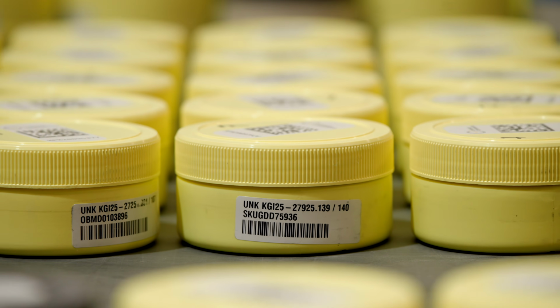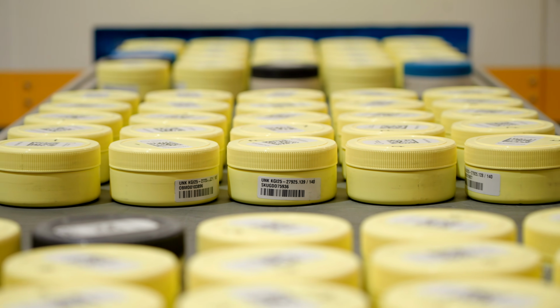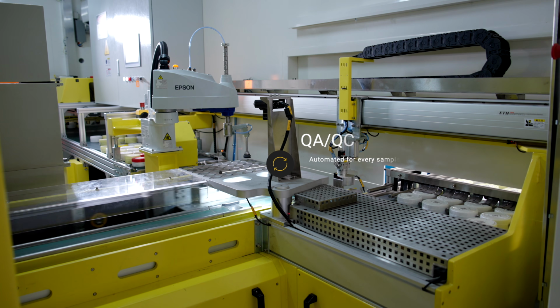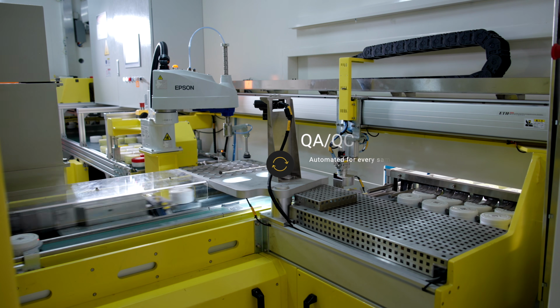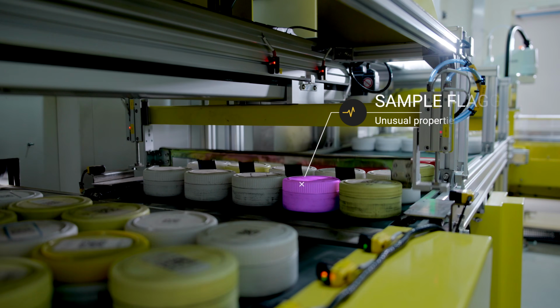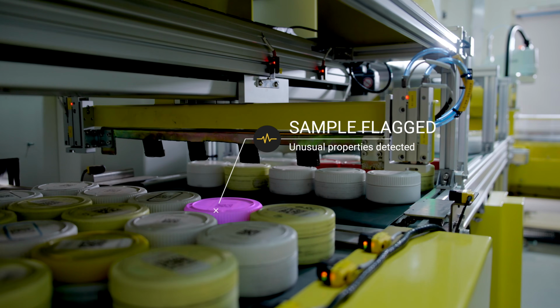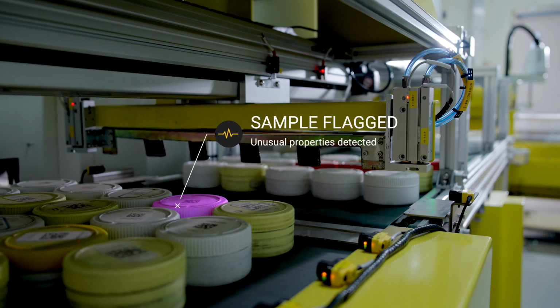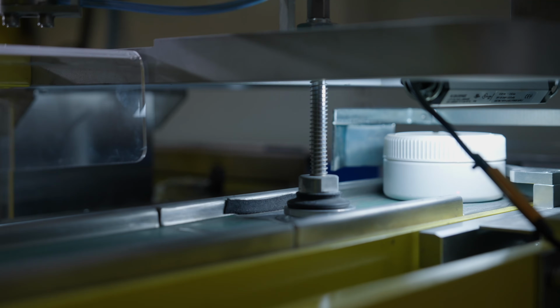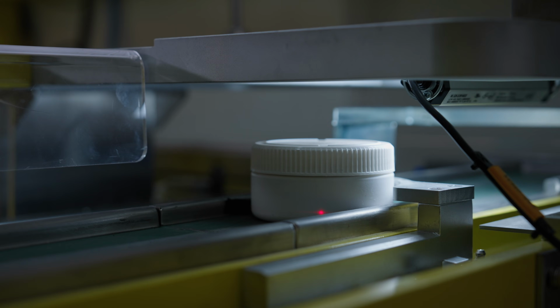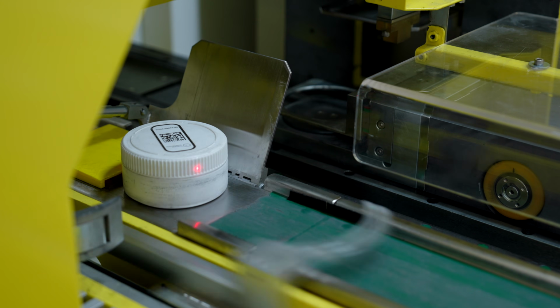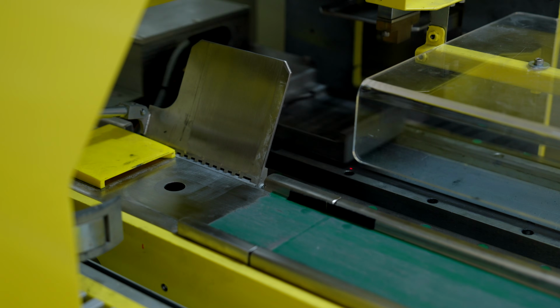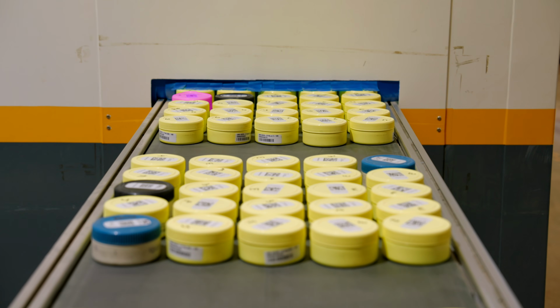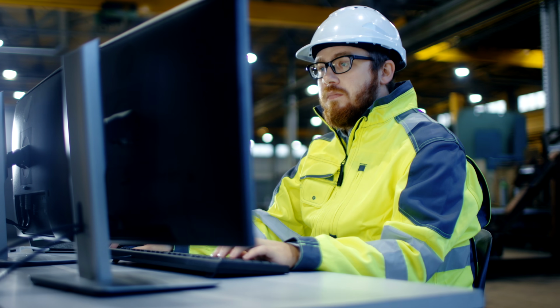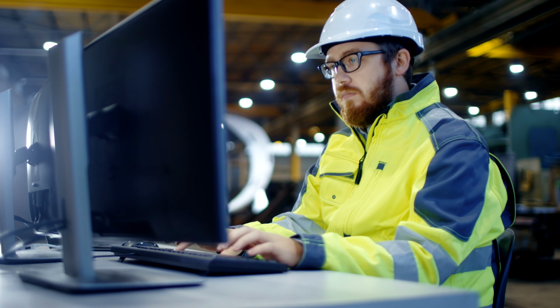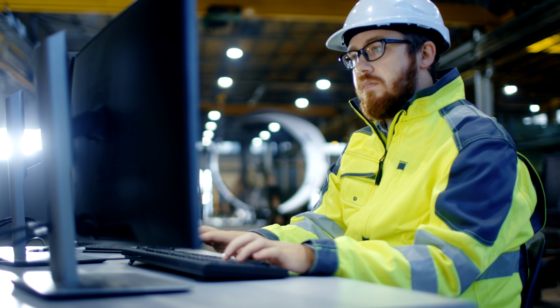Assay results are delivered digitally within minutes of a batch ending, complete with an instrument precision value calculated specifically for each sample. PhotonAssay also automatically performs a range of quality control checks and flags any samples with unusual properties. For example, these include samples with high levels of naturally radioactive uranium or thorium, which lead to decreased analysis precision. Samples where a correction is automatically applied for the presence of interfering elements, such as those used in the reference disk. And unusually heterogeneous samples, typically indicating the presence of coarse or nuggety gold. All results integrate seamlessly with Laboratory Information Management Systems, or LIMS, and Mine Information Systems.